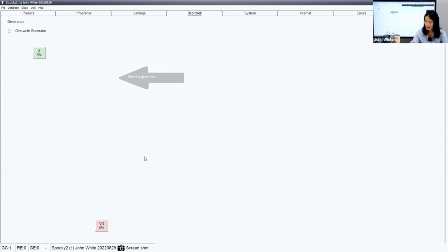And here I must say that if you are running contact mode, there are two cautions you must pay attention to. People who have a pacemaker or electrical implants, please never use contact mode. And please never use more than one contact accessory on one person at a time. By one contact accessory, I mean a pair of TENS pads. This is one contact accessory. You should never place two pairs of TENS pads on one person at one time, which can be dangerous.